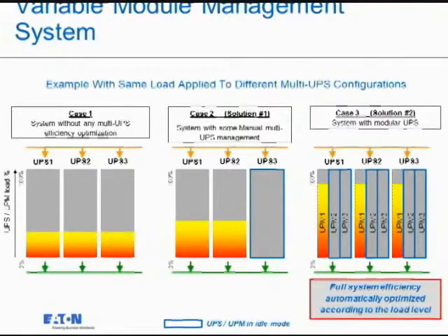Well, why would you want to do that? Because now I can choose not to utilize 2 of those modules. Now that 550 kVA becomes 150 kVA. How complicated? About 1.6 milliseconds. Well, how do I bring it back on? About 1.6 milliseconds.